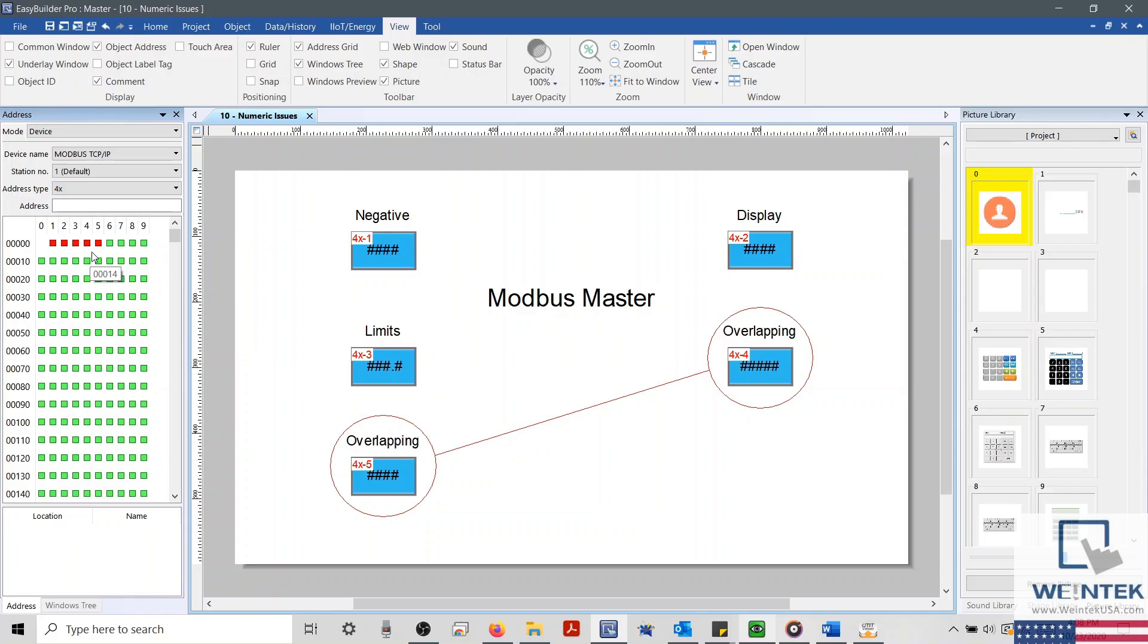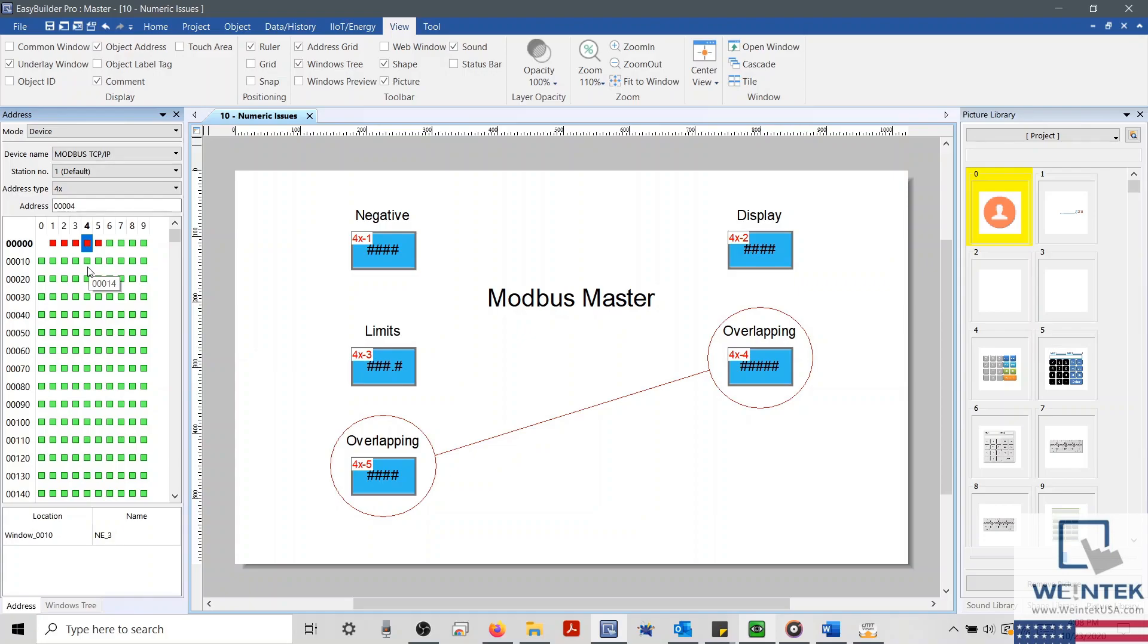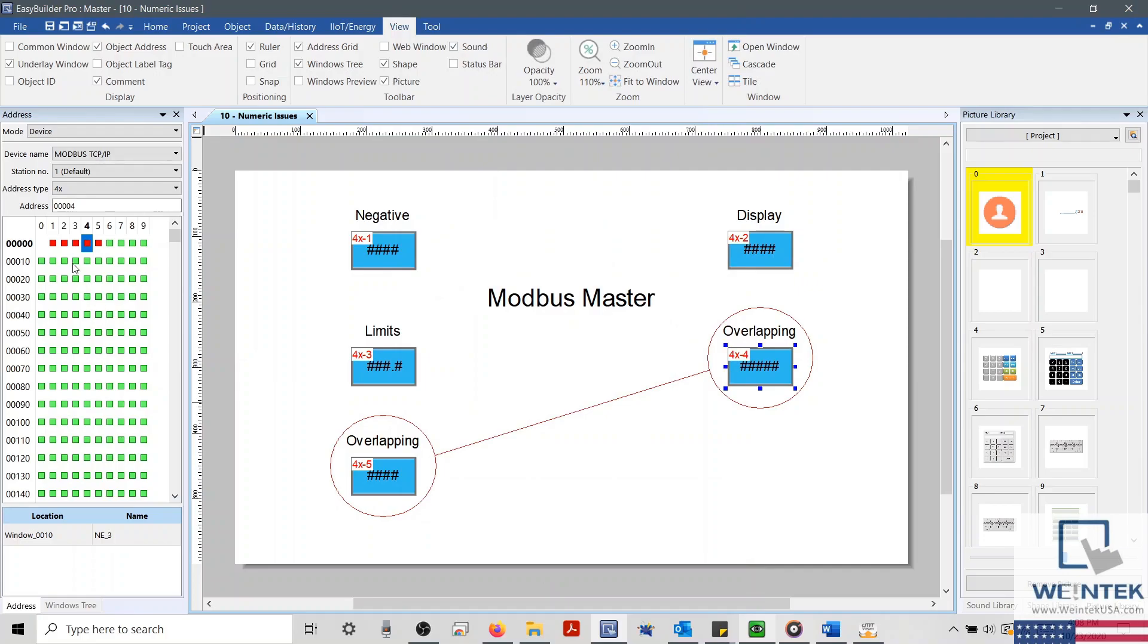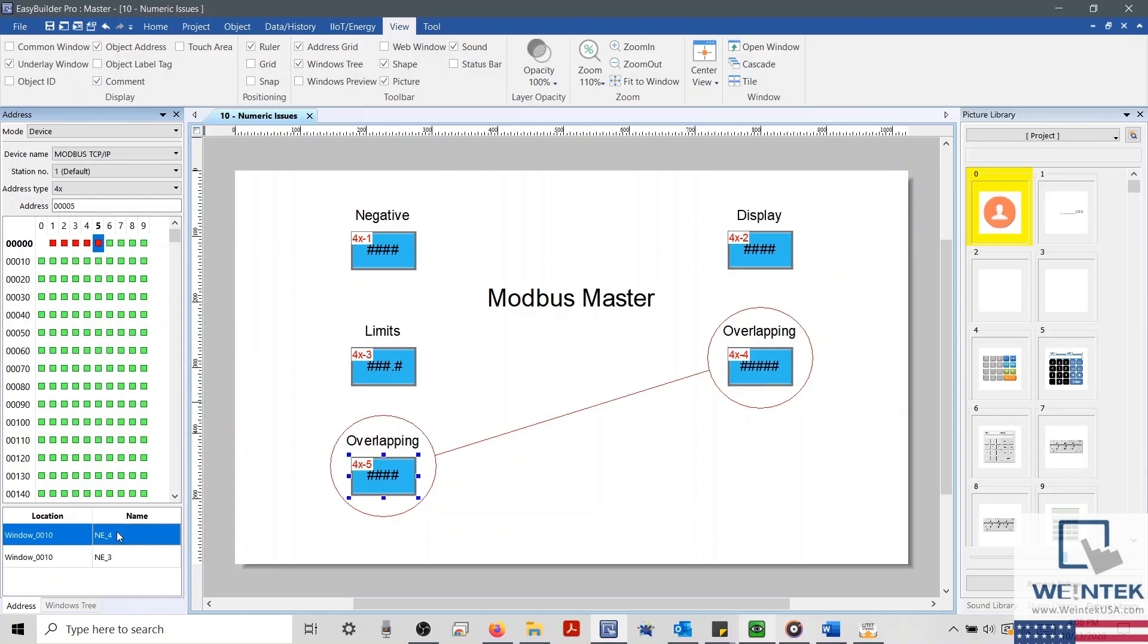We know that the registers we're trying to access are 4X4 and 4X5. We'll select both blocks within our Address Grid, and then take a look at the objects tied to each register within the dialog box below. Selecting 4X4, we can see that we have one numeric object on window 10. And if we double-click this object, we can open both its settings menu and the window in which the object is placed. Now we'll select the 4X5 block, and we'll find that this address appears to have two objects assigned to this register. And one of these objects is the same numeric object shown within our 4X4 block.